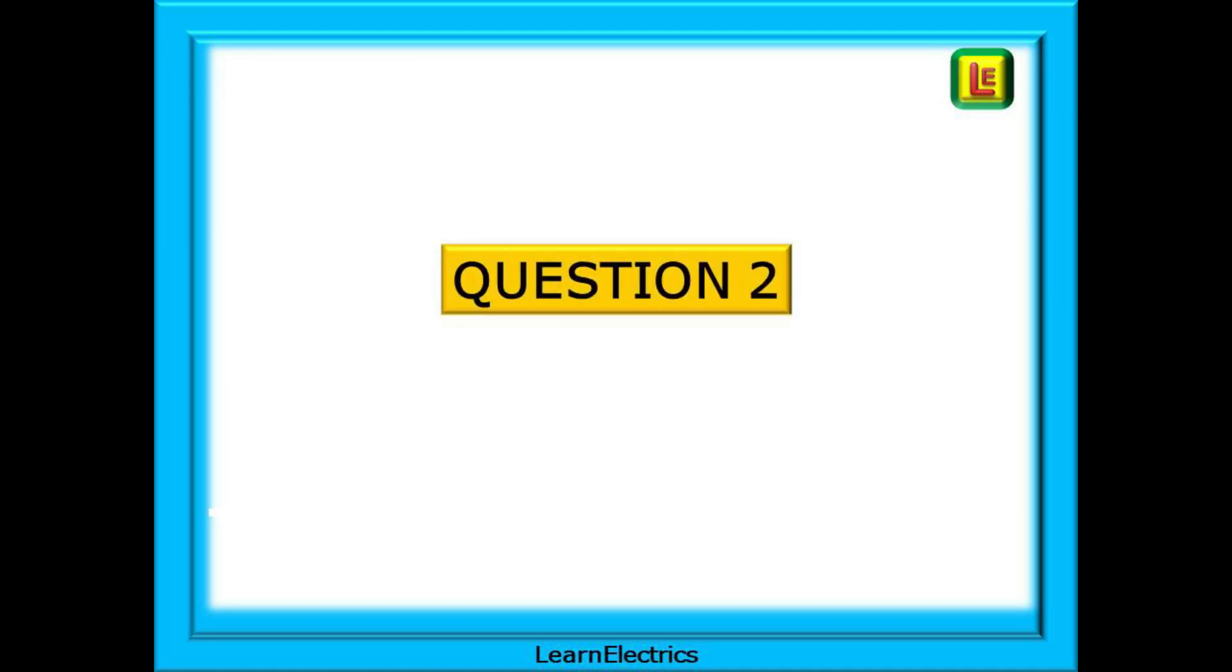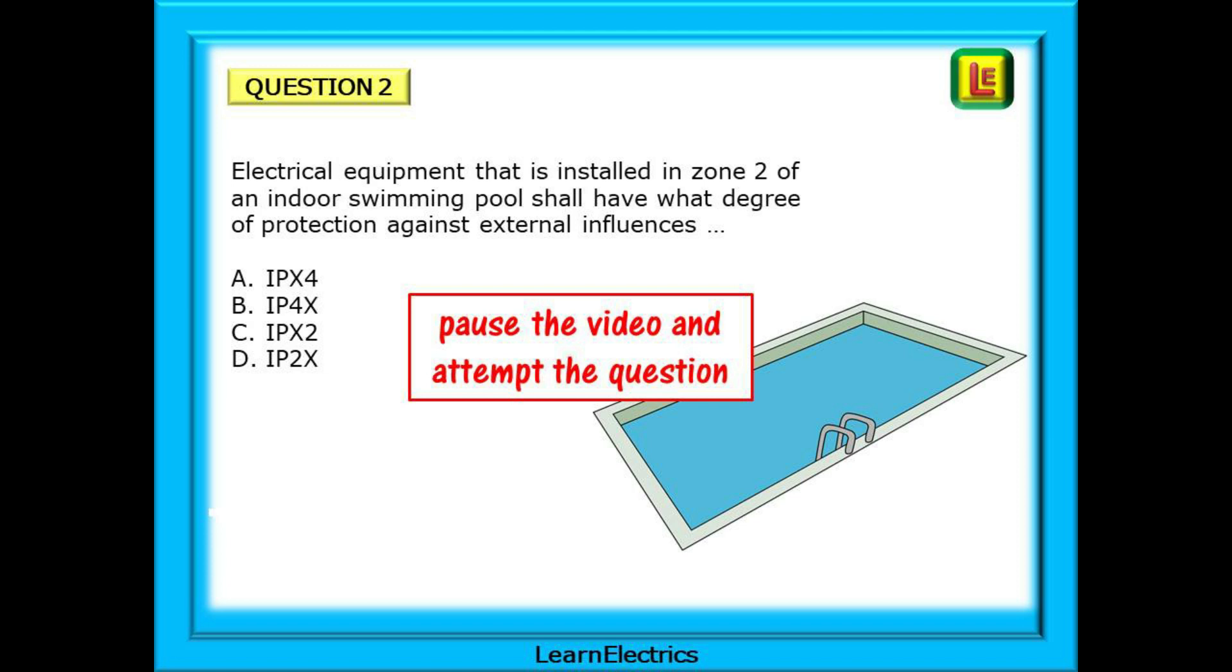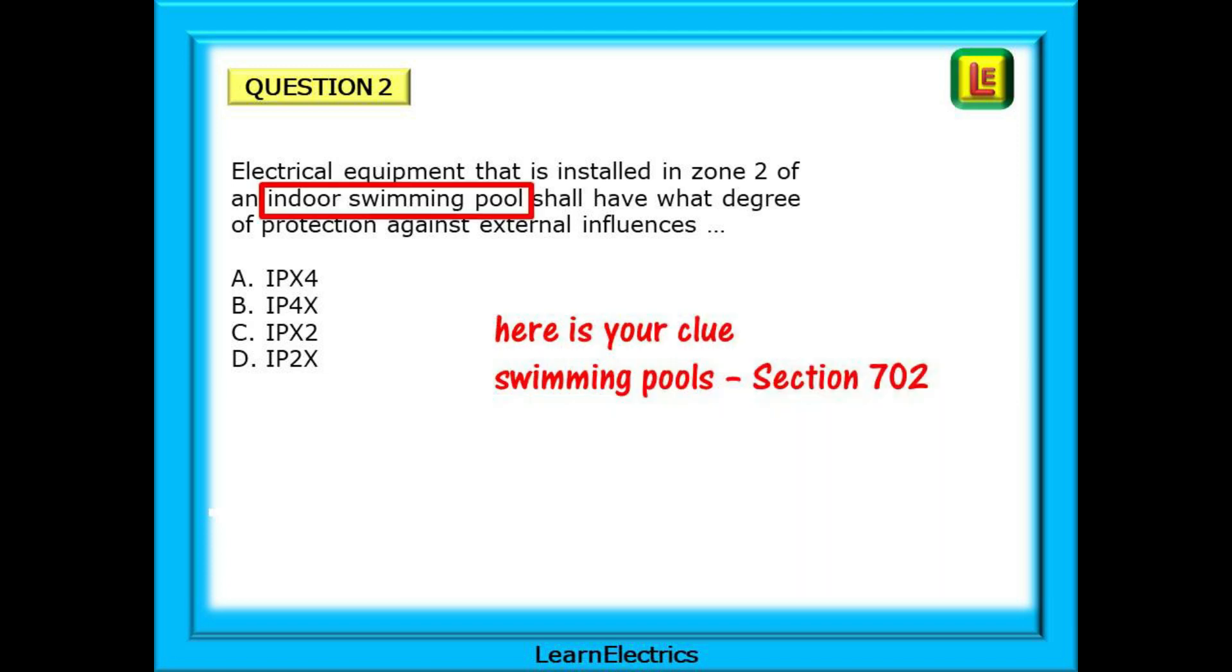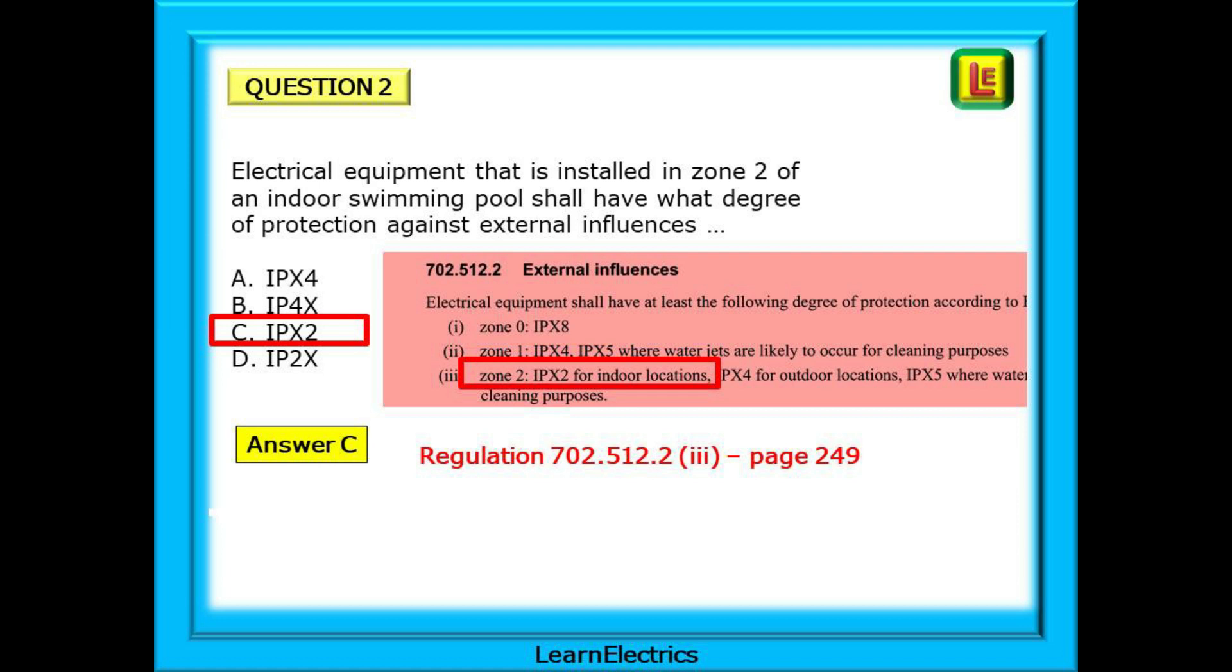Look at question 2 now. Electrical equipment that is installed in zone 2 of an indoor swimming pool shall have what degree of protection against external influences? Pause the video and attempt the question yourself. Here is the clue from the question: Indoor swimming pool. Go to page 3 and find the section for swimming pools, section 702, and go there. In section 702 you will find regulation 702.512.2 indent 3 on page 249. There is your answer for indoor locations: IPX2, Answer C. Make sure you choose the correct answer. IP2X looks similar but it is not right. It must be IPX2.